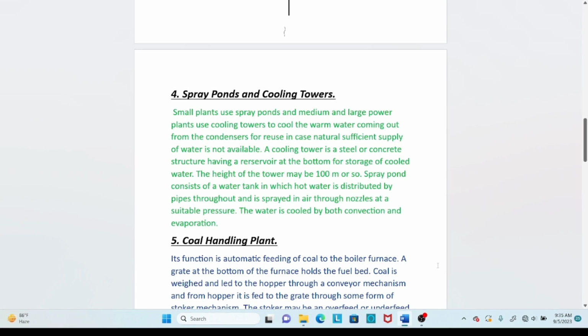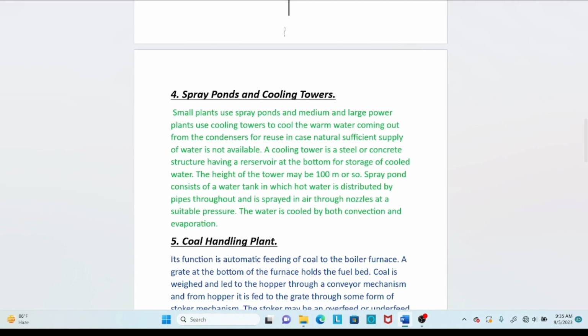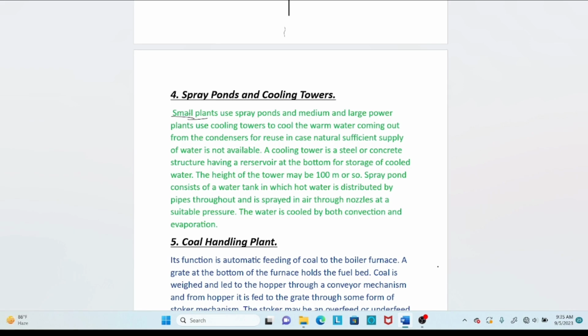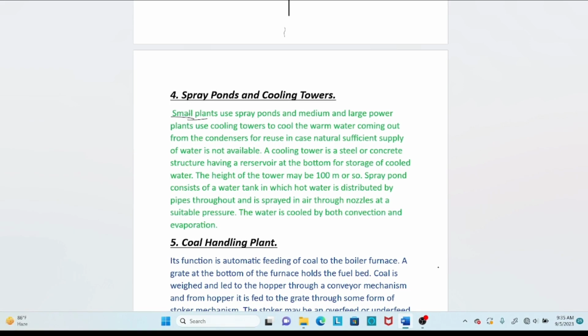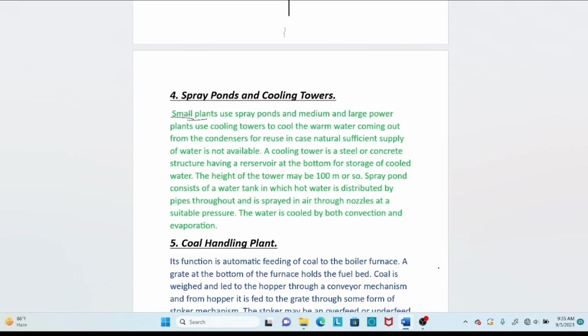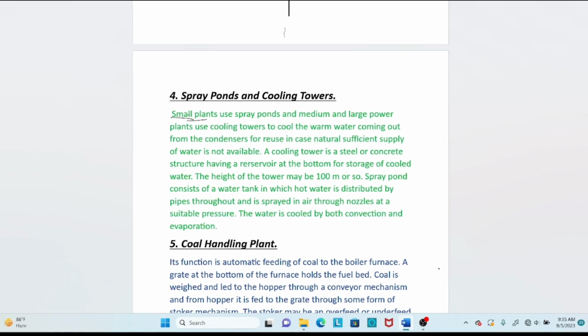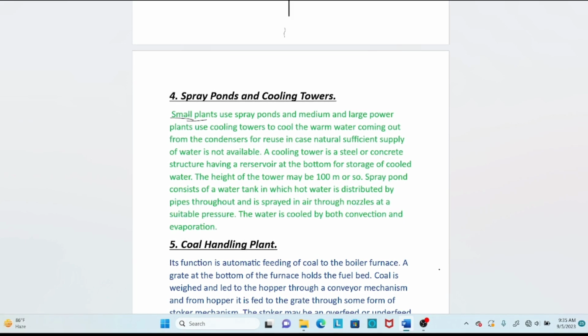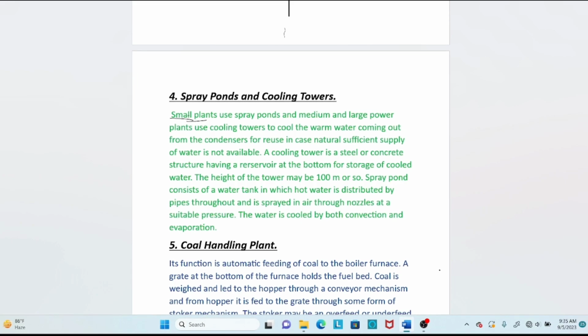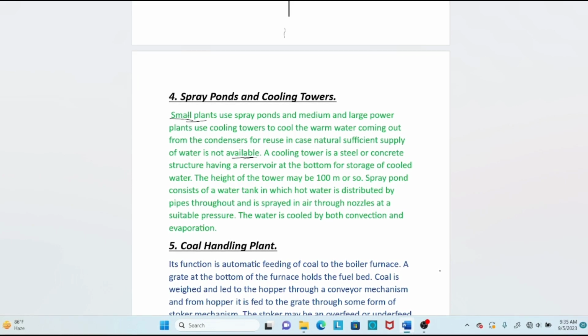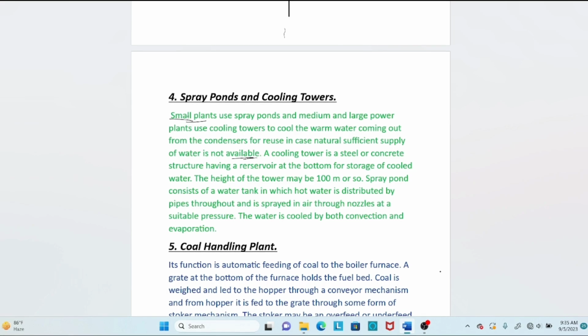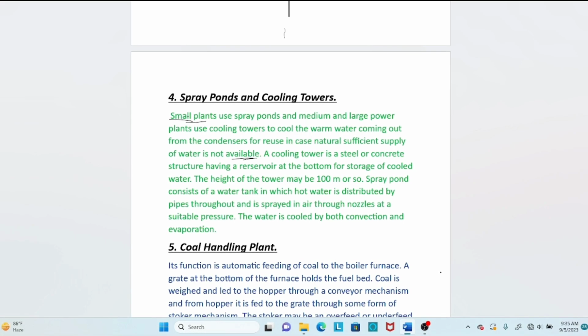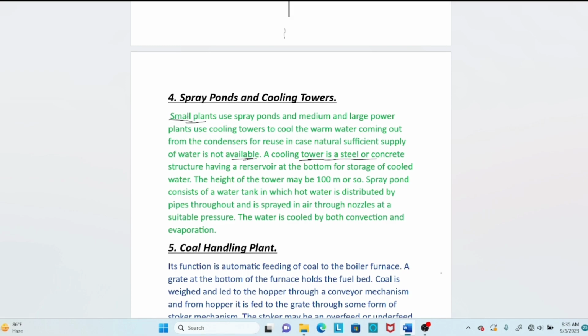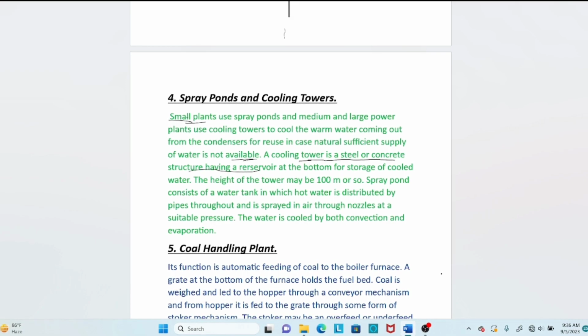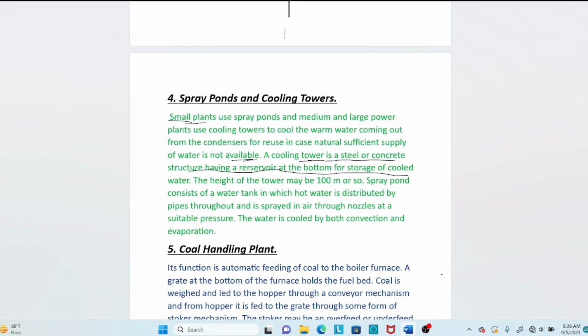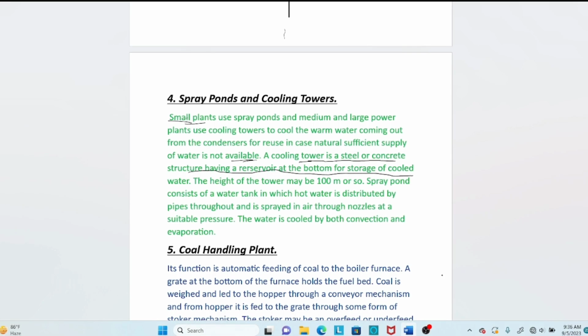Small plants use spray ponds and medium and large plants use cooling towers to cool the warm water coming out from the condensers for reuse, in case a sufficient natural supply of water is not available. A cooling tower, this is the main point, is a steel or concrete structure having a reservoir at the bottom to store the cooled water.